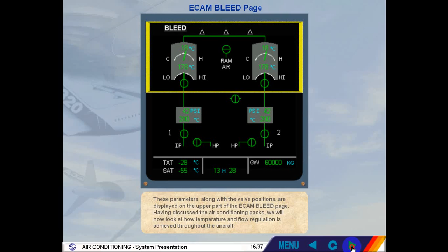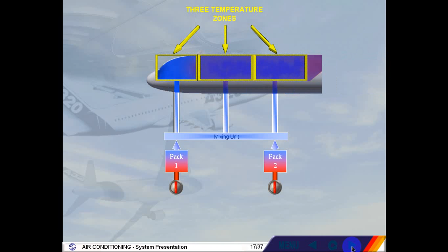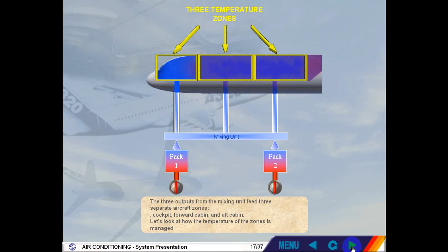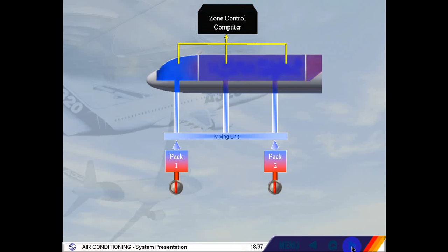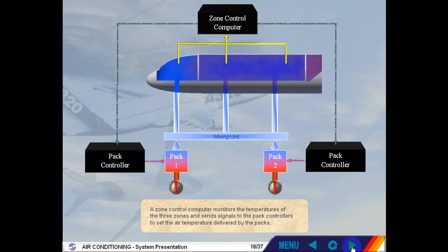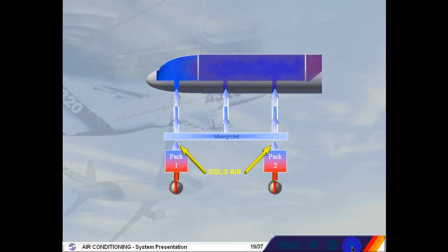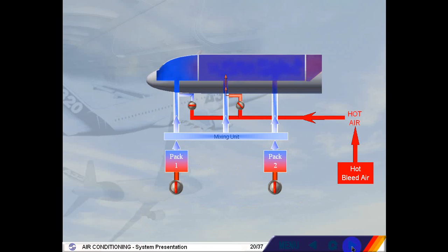The three outputs from the mixing unit feed three separate aircraft zones: cockpit, forward cabin, and aft cabin. Let's look at how the temperature of the zones is managed. A zone control computer monitors the temperatures of the three zones and sends signals to the pack controllers to set the air temperature delivered by the packs. Normally, cold air is delivered by the packs and is then sent to the three zones. Since the different areas of the aircraft may require different amounts of cooling or heating, hot bleed air can be added via trim air valves to obtain the demanded temperature for a zone.